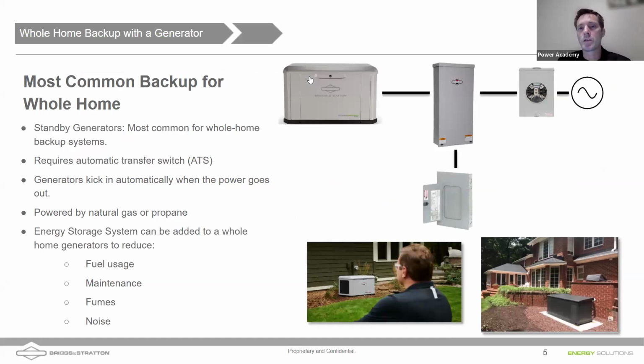They've been using a generator, they've been using an auto main sensing transfer switch, and when the grid goes out, that transfer switch will connect the generator to the loads of the house and disconnect from grid. This is the typical way of doing this, but times are changing. Battery and inverter systems are getting bigger and stronger and capable of backing up whole homes at a more cost-effective point now as well. Nice things about generators are, of course, you get long run times. You can essentially run indefinitely if you're running off of a large natural gas supply, and even propane tanks.